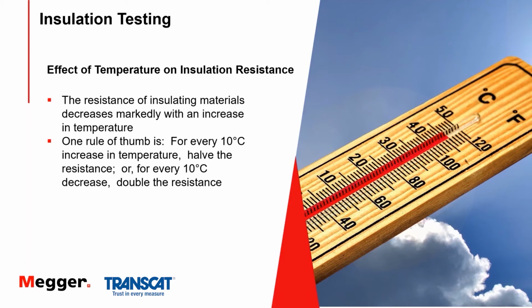As a general rule, we'll come back to this several times, but this is just to give you a general idea: a 10 degrees centigrade increase in temperature typically cuts insulation values about in half.